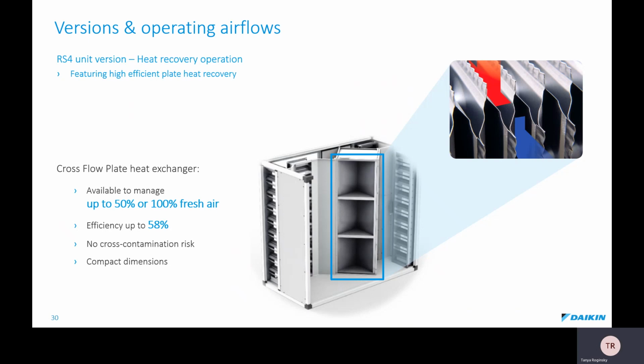The cross-flow heat exchanger is available in 2 versions. The first one is to manage 50% of fresh air, and the other one is to manage 100% of fresh air. The efficiency of the heat exchanger is up to 58%. There is no risk of cross-flow contamination, which is critical during a pandemic. The dimensions are compact.